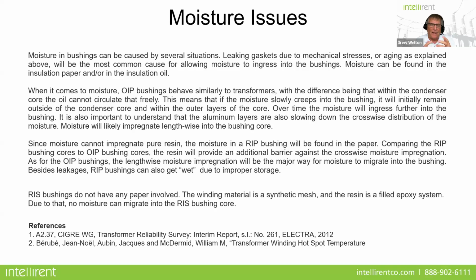But since it can't circulate in a bushing, that means that moisture slowly creeps into the bushing. It'll initially remain outside the condenser core, within the outer layers of the core. So over time, the moisture will ingress further into the bushing. It's important to understand that the aluminum layers are also slowing down the crosswise distribution of the moisture. So moisture will likely impregnate lengthwise into the bushing core.